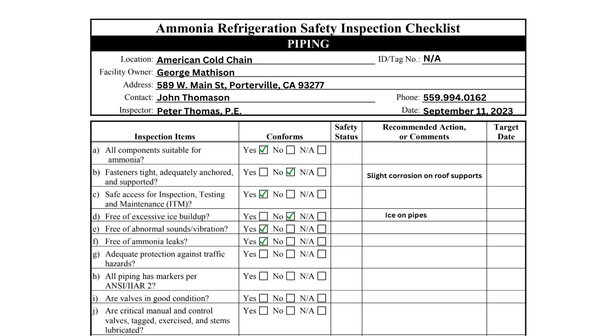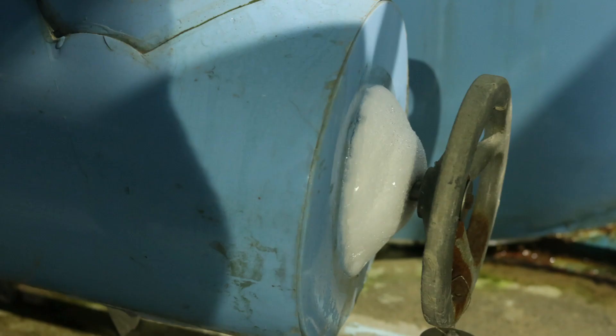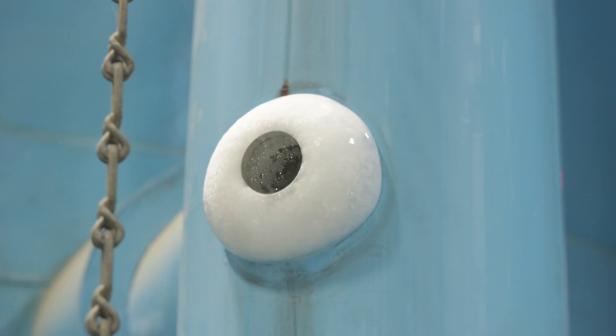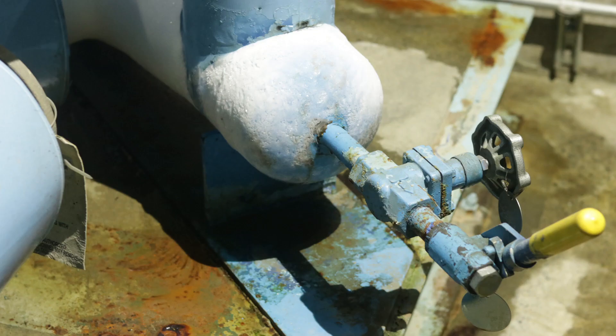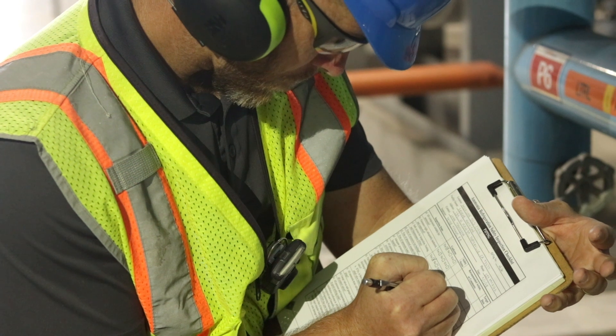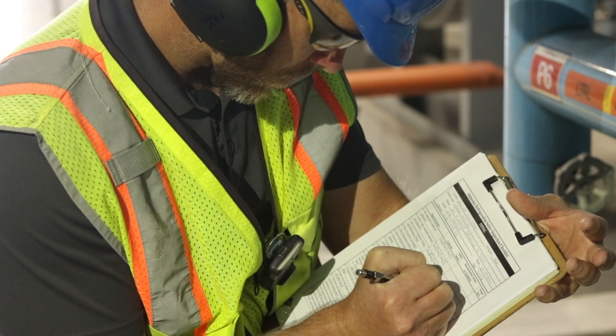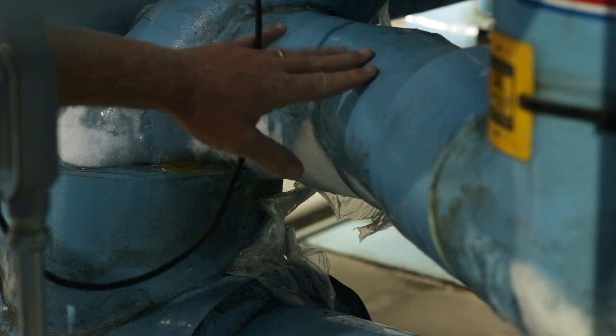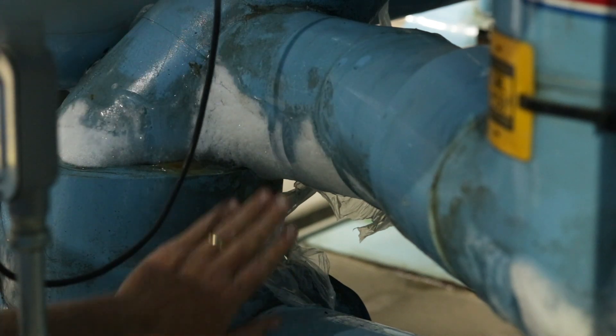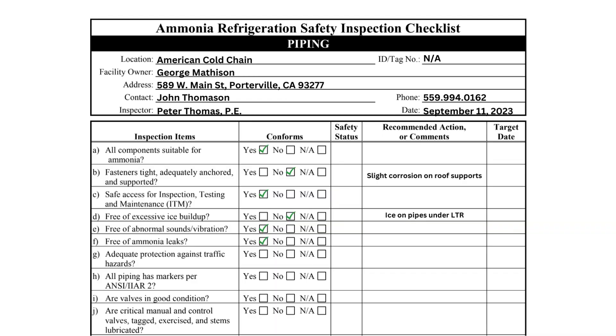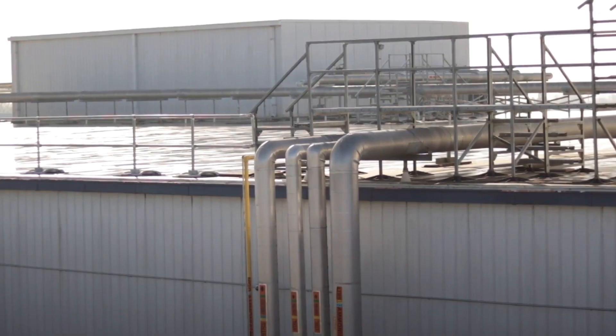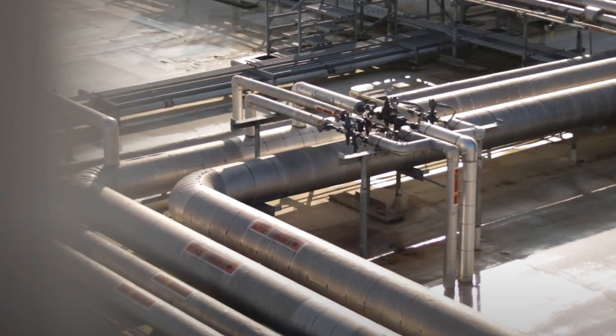Checklist items D, E, and F inquire about leaks and other piping abnormalities. The inspector must do a visual inspection of the entire piping network to verify the equipment is free from vibration and leaks. Item D directs the inspector to check for ice buildup, which is possible to see on the low side of a system. There is some ice buildup on the pipes underneath this recirculator, which should be recorded. Item F asks specifically about leaks. Many pipes are located outdoors, making it more difficult to detect a leak.